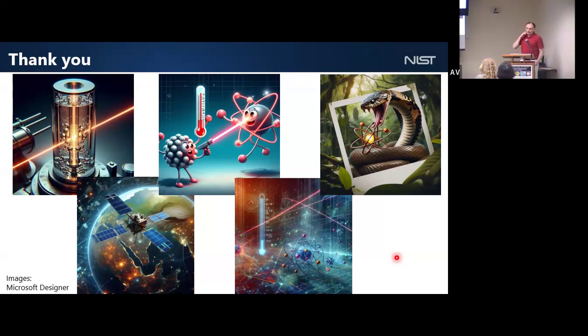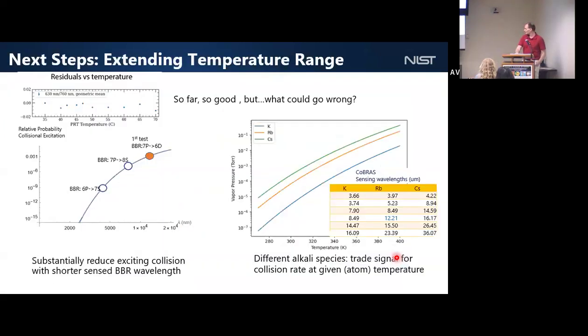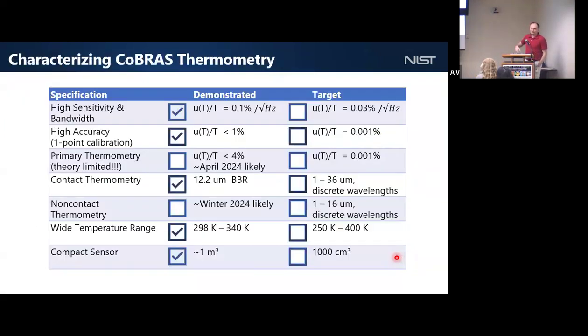So just by simply changing the frequency of your laser, you can tune the CoBRAS sensor to sense different wavelengths. And we can also swap in different filters on our fluorescence detector to sense different wavelengths from the same excitation laser, like I was demonstrating with the different fluorescence wavelengths. So one single sensor has the capability to measure several wavelengths in the few micron wavelength regime.